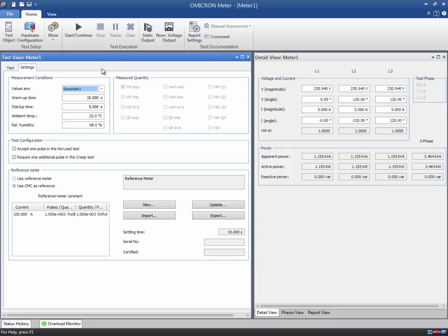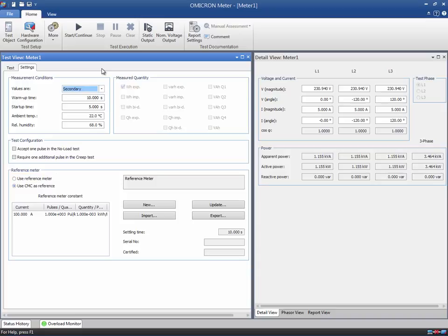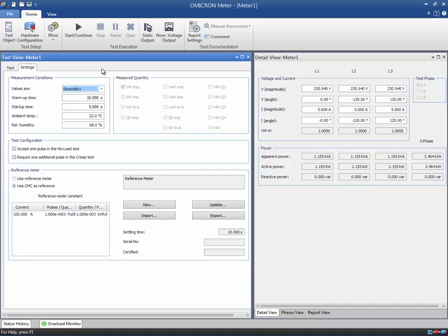As mentioned in the previous video, we will be using the CMC as a reference. However, you can still use an external reference meter as your reference. This reference meter's accuracy is then the reference accuracy for the error calculation. The reference meter data has to be specified, including the meter constant. This data can be updated, imported, and exported for later use.